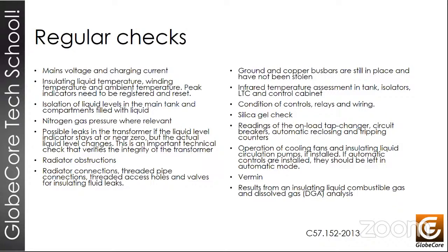Sometimes there have been transformers that after furan analysis show that they have 15% useful life left, and the owner of the equipment wouldn't even know about it, and they would allow the equipment to continue working without any corrective action whatsoever. And worst of all, they wouldn't even take a forecast for the future life, knowing that the transformer is in rather bad condition. So therefore, it's very important to be able to receive information, but it's actually even more important to know what to do with it and how to analyze it. And if you can go to the next slide.